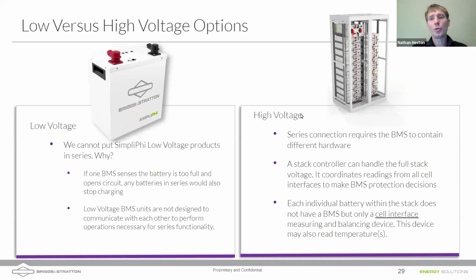And then we also have high voltage stacks. Typically for large battery systems, it makes sense to go to high voltage because you're moving so much current at low voltage to produce the same power. One way to avoid having to use enormous wires, like 500 kcmil, for instance, would be to increase the voltage and decrease the current.